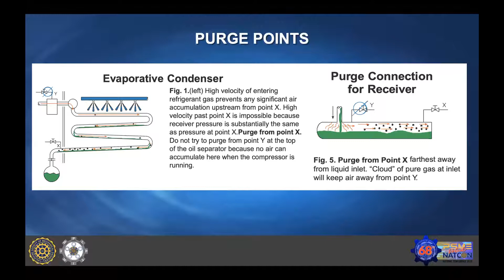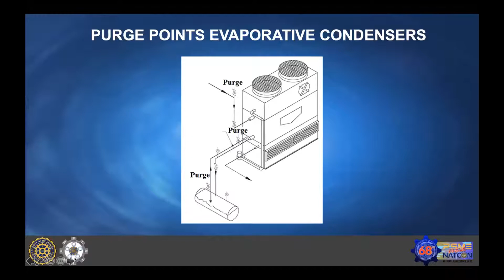You can see here, your purge points can be taken from a common header, or for automatic purging it has to be at the outlet of the condenser. These are the typical examples of the purge points. For a PHE condenser, it can be taken at the outlet of the PHE, or for an evaporative condenser, this is the purge point. These are the atmospheric condensers or open type condensers. You can see a purge point taken from the header of this condenser.